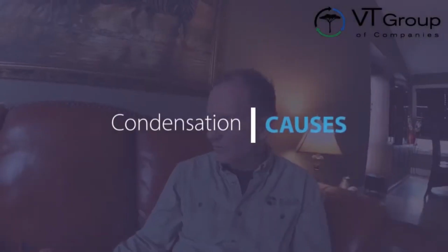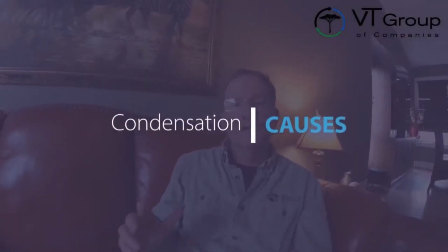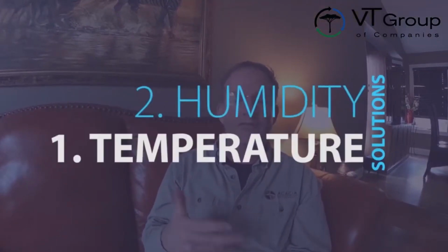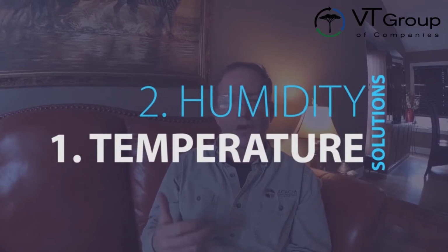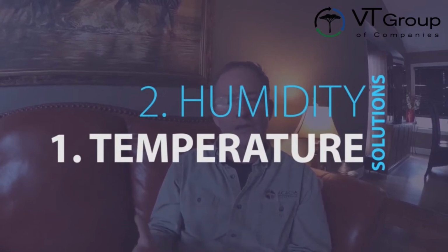When we get condensation on windows, there are normally two reasons. One, our moisture level in the home has gone too high and we're hitting what we call dew point. Dew point is when the moisture falls out of the air, and that's the condensation that starts to form on your windows. If the surface temperature of the window is cold enough and the relative humidity is high enough, we're going to get condensation. So there are really two solutions. One, you change the temperature of the glass. How do you do that? You upgrade your windows. The alternative is to change the humidity.